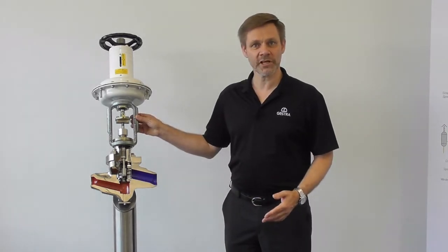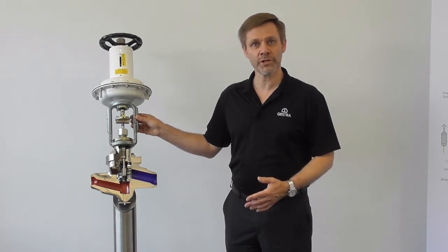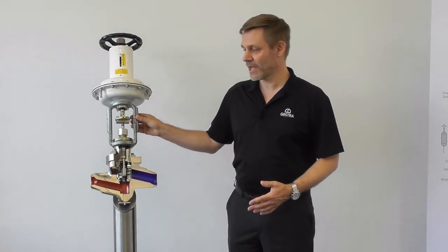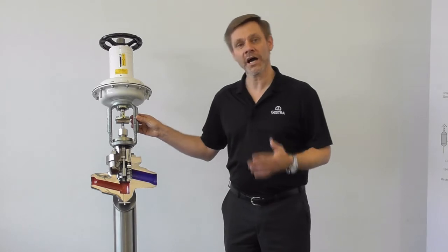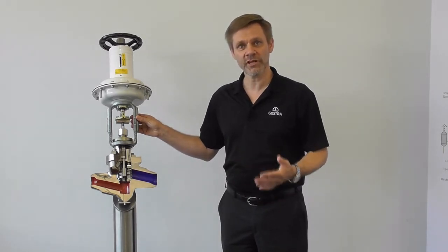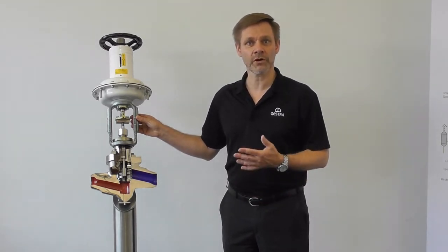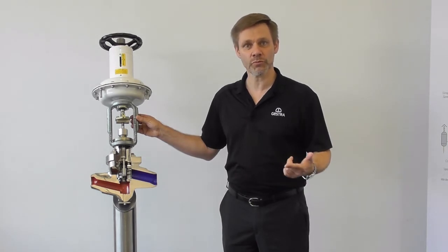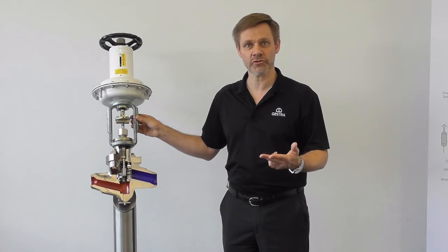It's a valve according class 900 or the nominal pressure PN160 and it's designed to handle the high differential pressures in the steam water cycle where we are facing flashing water, cavitation problems and high flow velocities by high differential pressures.